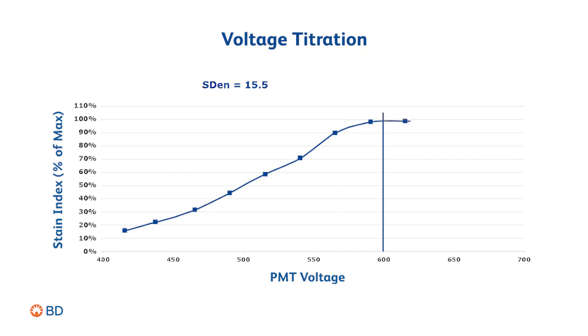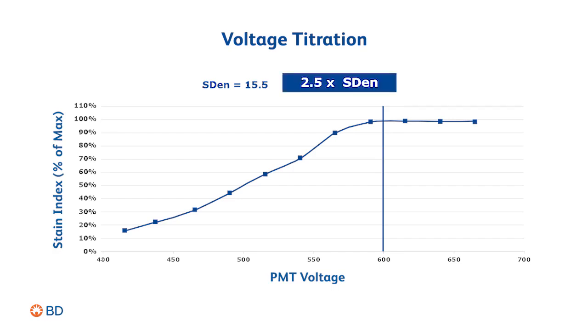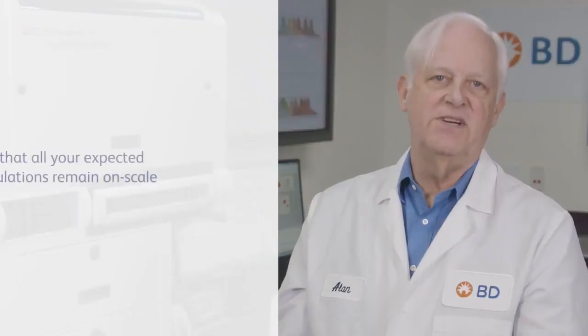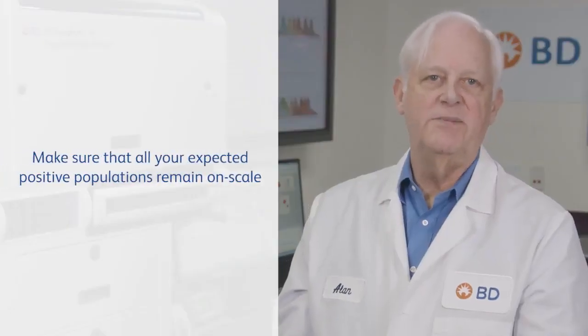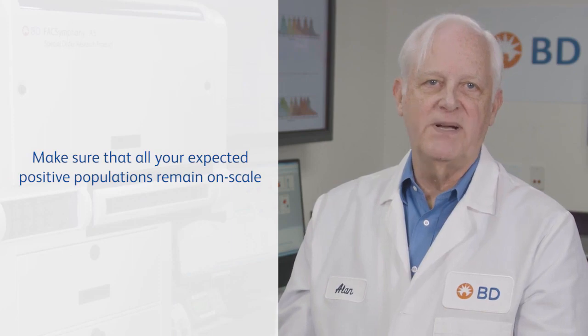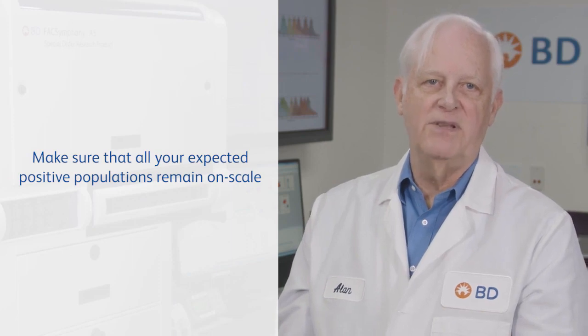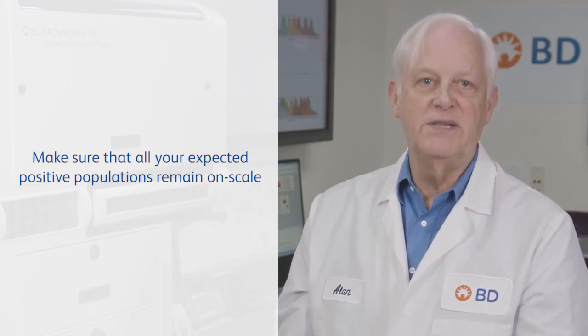In this example, the detector should be set to approximately 600 volts. At this voltage, the robust standard deviation of the negative cells is, as expected, two and a half times the electronic noise. When making these adjustments, always make sure that your expected positive populations remain on scale.